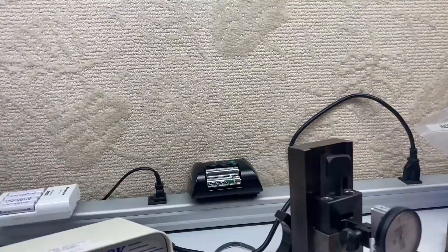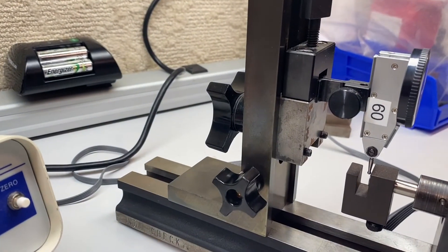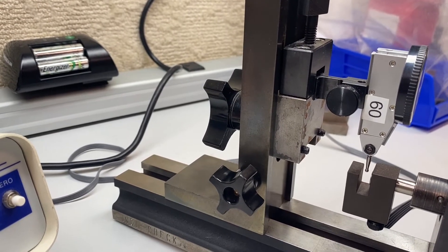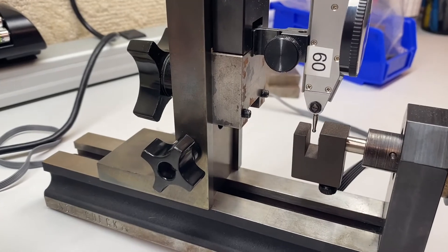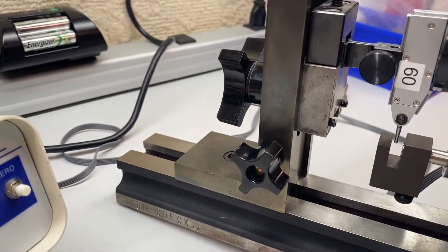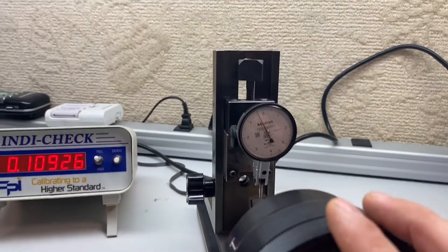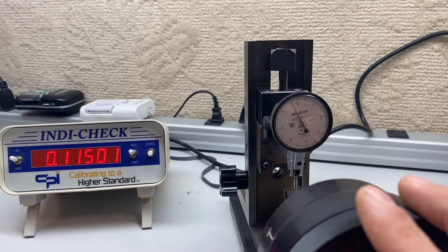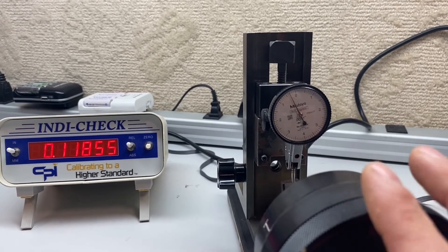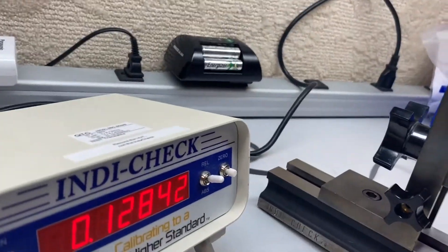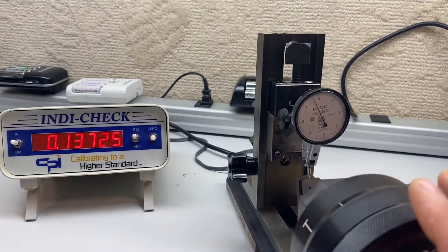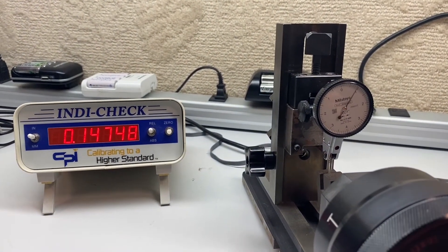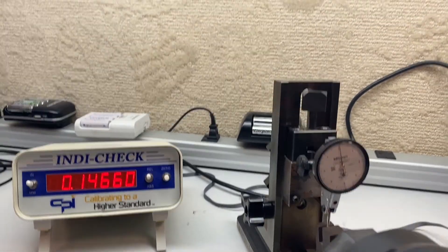And then we'll come over here and do this same test, but pulling. Making sure that face is barely contacting the head, the measuring tip. You don't want to hit the shaft up there. I'm going to come back around once it begins to read. Just indexing. Not even close. There we go. Right about there. Set the camera up.